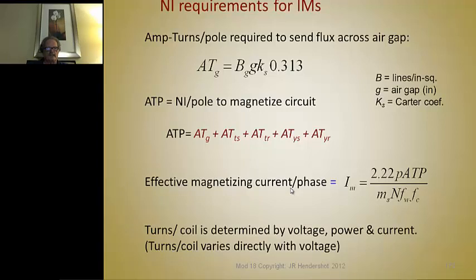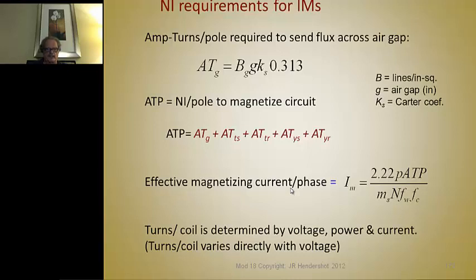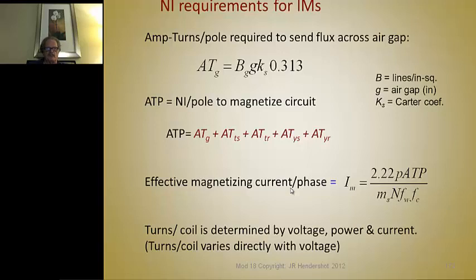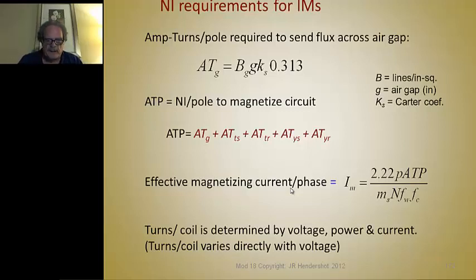If you double the voltage — changing a winding from one voltage to another — you double the number of turns and go to three wire gauges finer, which gives you the same cross section of copper. Three wire gauges finer and double the turns per coil doubles the voltage. Conversely, if you want to halve the voltage, you go to three gauges fatter wire and reduce the number of turns by half.